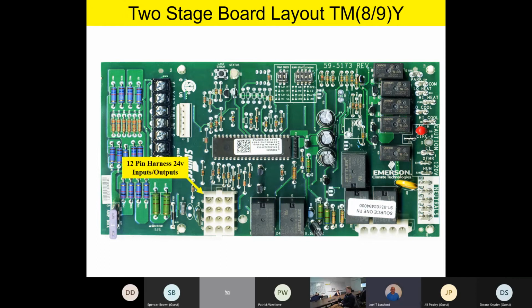As we move around the board some, we see we have a 12-pin harness, and that's going to be 24-volt inputs and outputs to key components like the pressure switches, the rollout switches, the high temperature cutout switch, and so on. And the gas valve will all be harnessed in on that 12-pin harness. If you take a look at your install information and your technical information, you'll see that there are some schematics in there that you can get more detailed on pin to pin. But basically that 12-pin harness is where we have our inputs and outputs to those key components, like I said, our gas valve and pressure switches and safety circuits and so on.